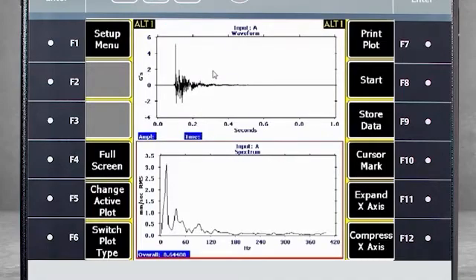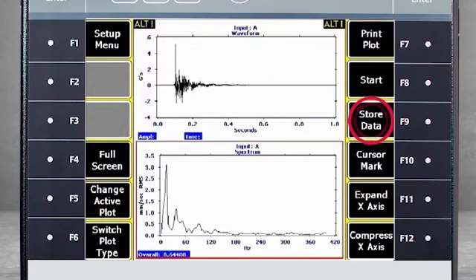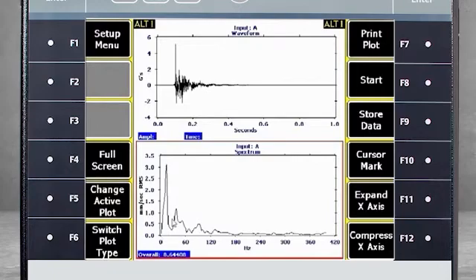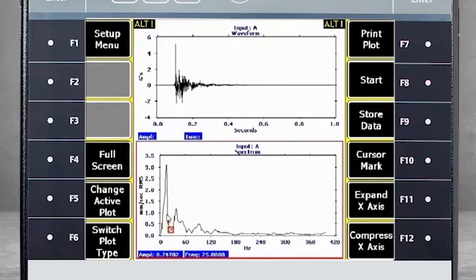Here you see the impact in the waveform and the averaged spectrum below. This data can be stored in job mode by selecting F9 Store Data. To identify the natural frequencies, I can add a cursor to scroll over the peaks. The first natural frequency is 14 Hz, and the second one is around 37 Hz.